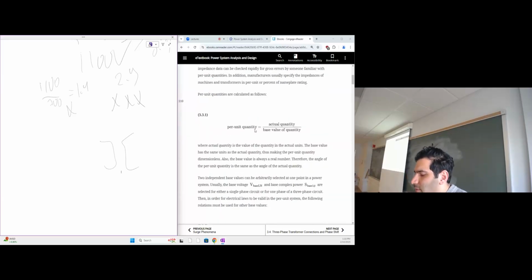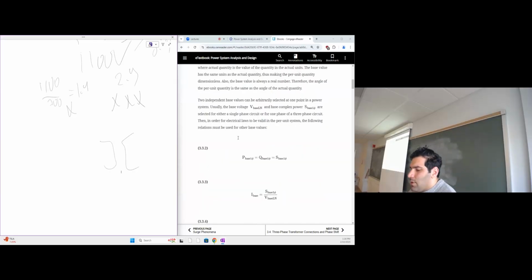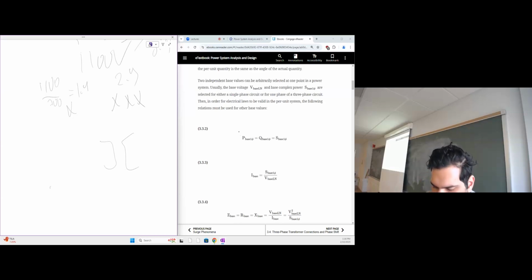So the per unit quantity is actually the division of the actual quantity by the base value of the quantity. The actual quantity is the given quantity by me. I would say we got that measurement at that place. It came out to be that much. The base value is normally selected by you, but I will usually determine that base value. Because you might choose 100 as a base value, he might choose 200, and that person might choose 500, let's say. So every one of you is correct. You are all good. But for me, it will make me solve the question 100 times or 60 times because each one of you might take a different value. So the base value is some agreed value, which we would like all of us to agree is the value used in the whole system. No matter how many sections we have, it's the commonly used base value. So typically we'll need to determine two base values, okay? One for S and one for V.